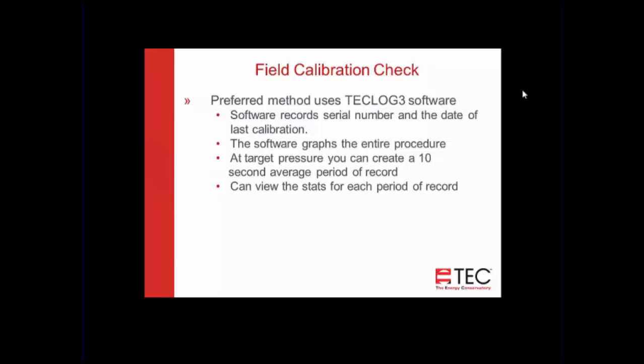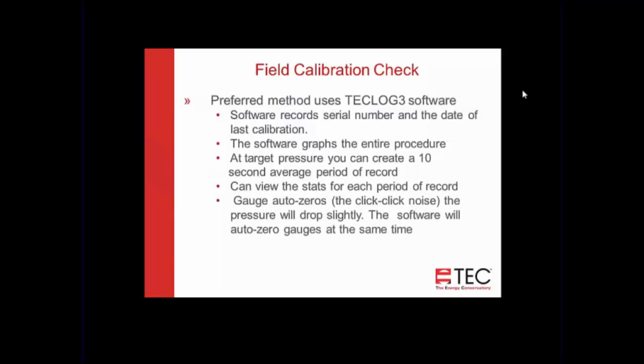You can see the 10-second average for each gauge during that period, and make sure it's within 1% of the requirement. If it's outside of 1%, then it will need to be sent in for calibration.